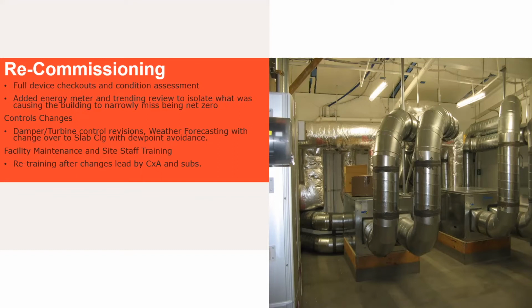Because there's a big difference in lag time. Say you're using the space temperature, and all of a sudden you bring it down to your 65-degree pre-cool. Well, it's going to rebound. You have thermal mass going on, and you're not going to pre-cool the whole building down to 65 degrees on the slab temperature, which is inside the slab, because then you'll drive the space down to 50 degrees with no lower limit. So you're not going to get that during summer, most likely. But we really started making adjustable implementation for pre-cooling and weather-based forecasting for slab cooling. And I should probably check in on this project to see how that's going.